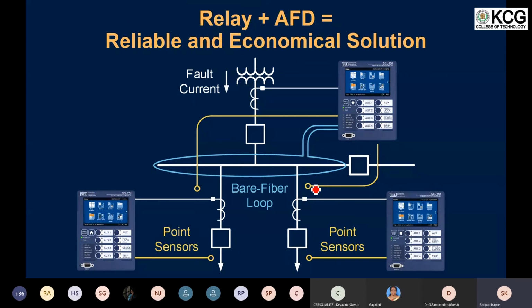These sensors basically look at the intensity of the light. When the intensity of light exceeds a certain threshold, along with that we also measure the associated current that is read by these CTs. Again, these are going to be fast overcurrent, like I explained earlier, because of the filters that we are going to use. So, combining the assertion from the fault current and from the intensity of light, these relays are going to trip.